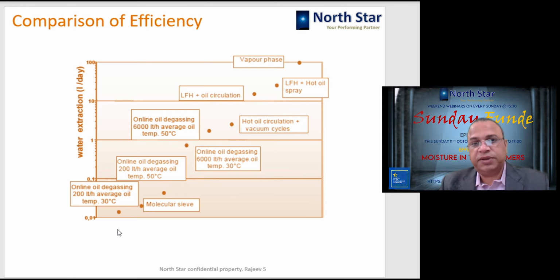And second is LFH plus oil circulation, and LFH plus hot oil circulation. So this is again second number effective process, followed by online degassing at a higher rate of filtration, that is 6000 liter per hour, and temperature is 50 degrees centigrade. Then hot oil circulation plus vacuum cycle can take around 1 to 10 liters of water per day. If you look at online degassing with a smaller capacity system, then it is around 0.1 to 1 liters of water per day that can be taken out.